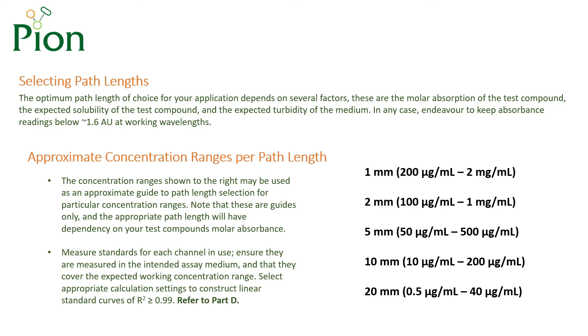This is because, at values greater than 1.6 absorbance units, you will begin to observe a loss of linearity in the relationship between concentration and absorbance, which will begin to introduce quantitative errors.